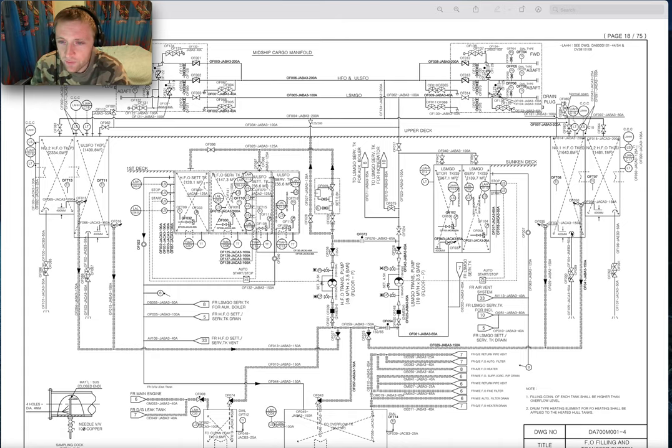We have also some drains placed here, and also we have the suction of the tank. The suction of the tank shows us that this is a quick closing valve, and also the suction pipe inside the tank is 400 millimeters distance from the bottom of the tank. That means there is always unpumpable fuel that remains inside, which is about 10 to 15 cubics, depending on the total square area of the tank.